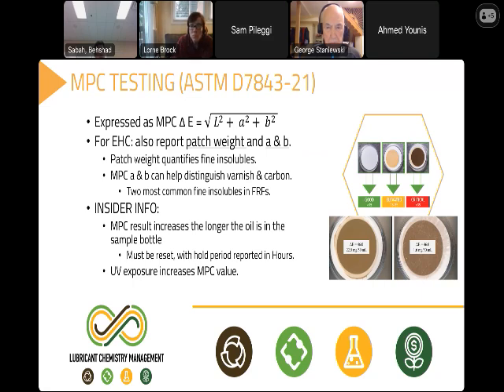But because mechanical systems are dynamic and we can have extreme pressure to low pressure in a millisecond, the material that's in this oil can transfer forms. So I would say there is really no safe MPC level per se. It would depend on the mechanical properties of the system. If you had constant flow, temperature and pressure, maybe you could say that there is an MPC value that would be safe. But when you dramatically change the conditions to which the lubricant is being exposed, this oxidation material that is accumulating in the oil is going to transfer forms. It's going to come out.